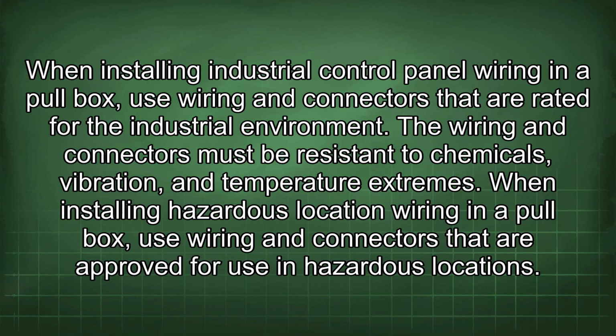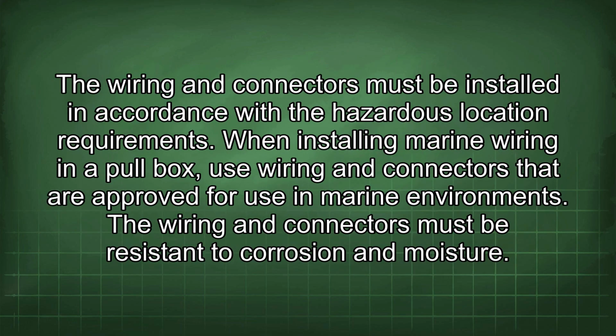When installing hazardous location wiring in a pull box, use wiring and connectors that are approved for use in hazardous locations. The wiring and connectors must be installed in accordance with the hazardous location requirements. When installing marine wiring in a pull box, use wiring and connectors that are approved for use in marine environments. The wiring and connectors must be resistant to corrosion and moisture.